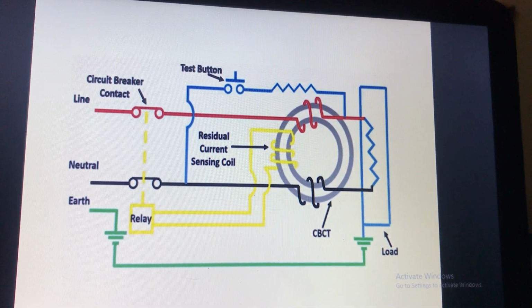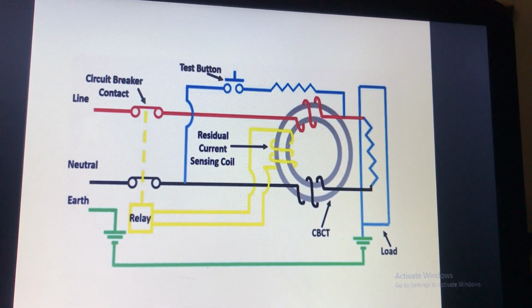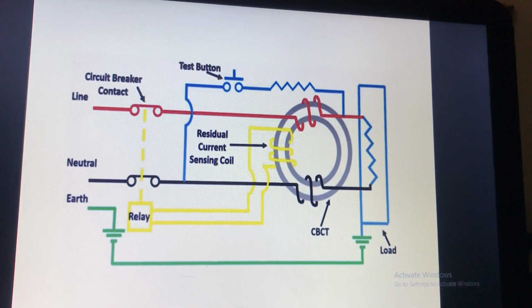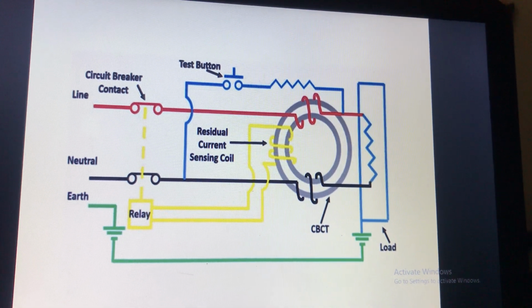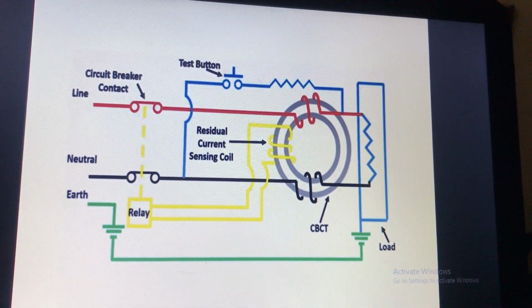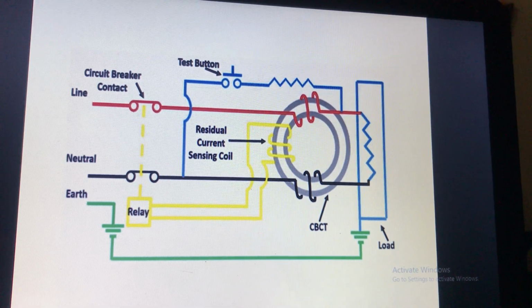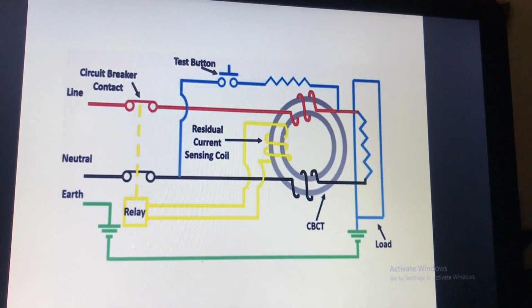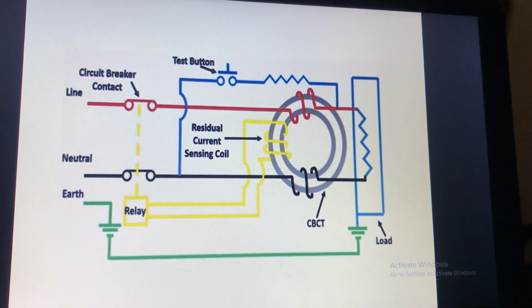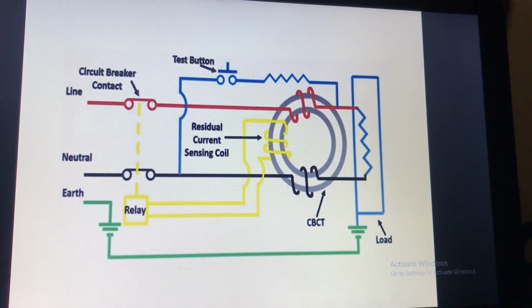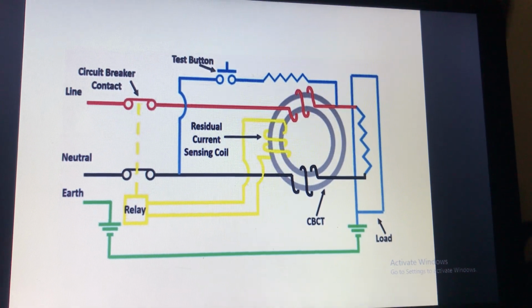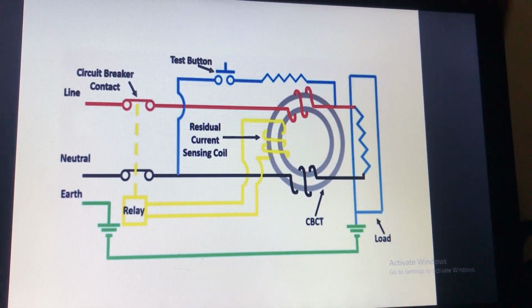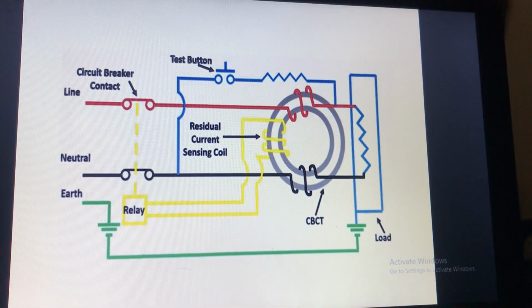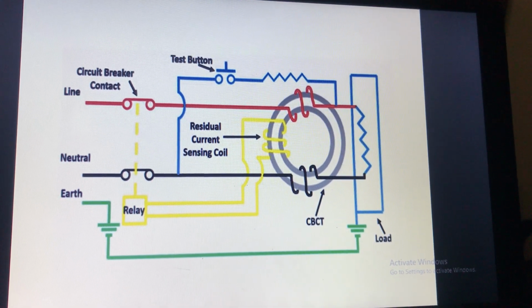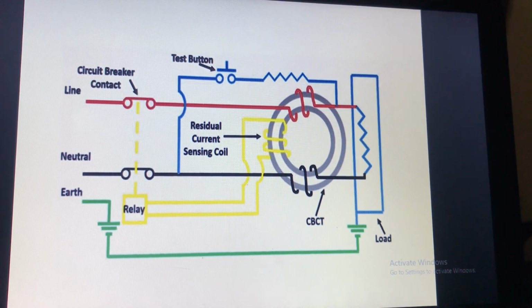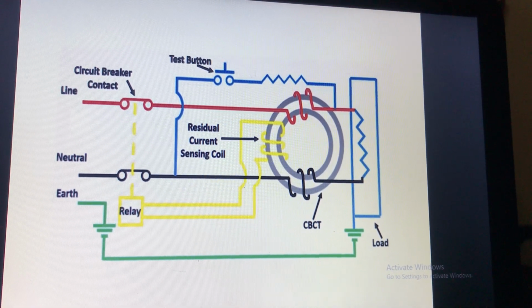Here you can see the diagram of RCCB. So here's the live wire. Red color wire is live wire and black color wire is the neutral wire. They both are on the transformer core. So in case of normal conditions, the current through both these wires is the same. So no flux gets induced in the transformer core. In case of any fault, in case of any residual current, this current gets imbalanced and EMF will get induced in this transformer core.